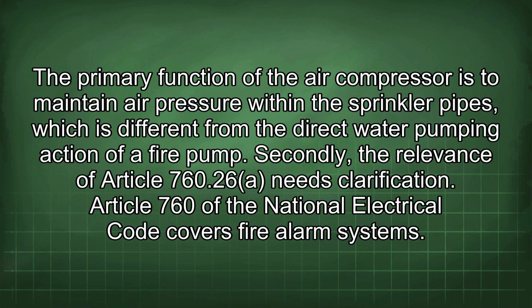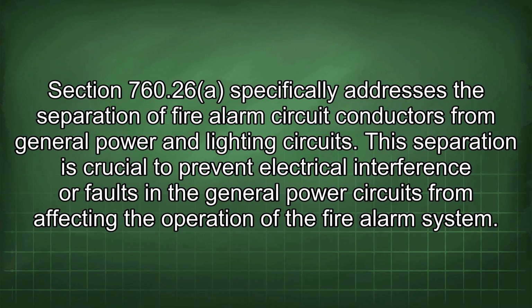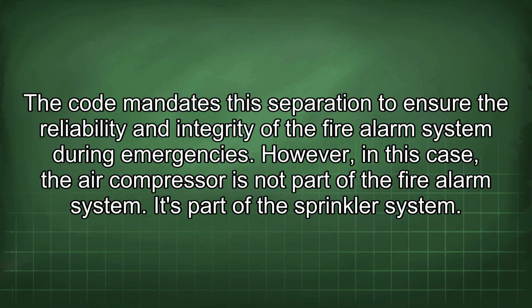Secondly, the relevance of Article 760.26 needs clarification. Article 760 of the National Electrical Code covers fire alarm systems. Section 760.26 specifically addresses the separation of fire alarm circuit conductors from general power and lighting circuits. This separation is crucial to prevent electrical interference or faults in the general power circuits from affecting the operation of the fire alarm system. The Code mandates this separation to ensure the reliability and integrity of the fire alarm system during emergencies. However, in this case, the air compressor is not part of the fire alarm system. It's part of the sprinkler system.